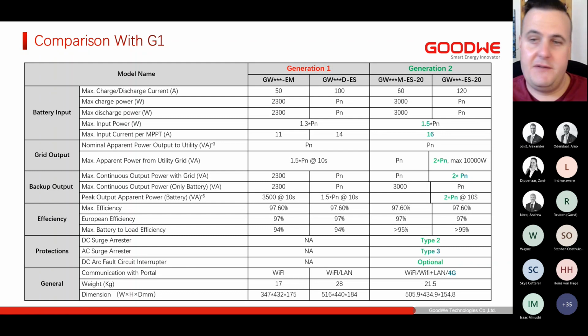So when you have solar and batteries, or when the grid is available, the inverter will allow you to do that overload constantly. It will not trip off for a constant overload as long as we have enough energy available from either the grid or solar and batteries together. Then when we only have batteries, it's only for 10 seconds. So when we have batteries only, our overload will only be for 10 seconds. And then we updated the DC surge arresters to type 2 internally. And then we can also get the optional arc fault detection as well.